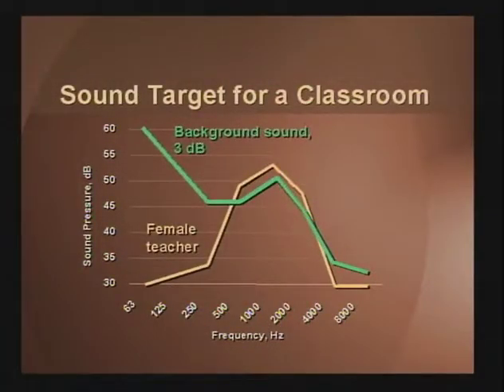This slide here shows what's happening. A teacher's typical voice is between 500 and 2,000 hertz in frequency. It's kind of spiked like the yellow line shown here. The green background line represents a typical background sound. It has a 3 dB clearance between the teacher's voice and the background sound, and it's spiking out about where her voice is. Typically, that might be diffuser noise in the space.